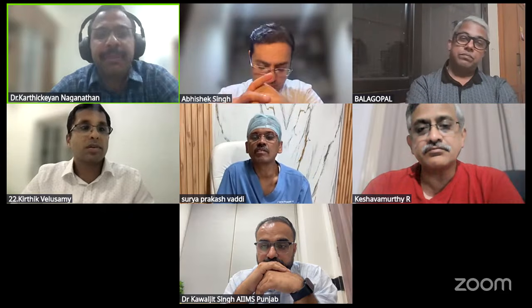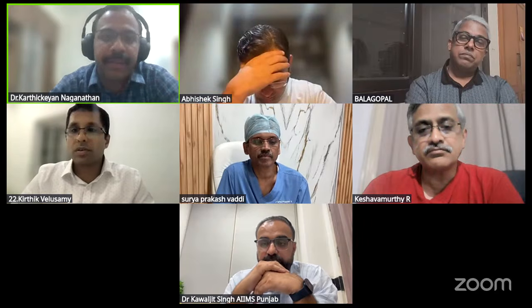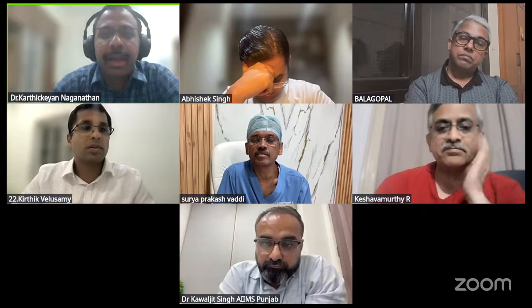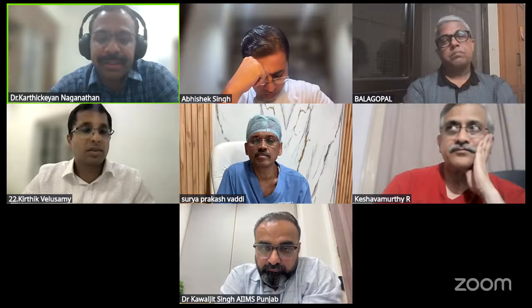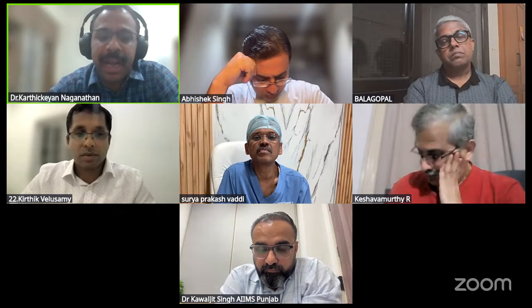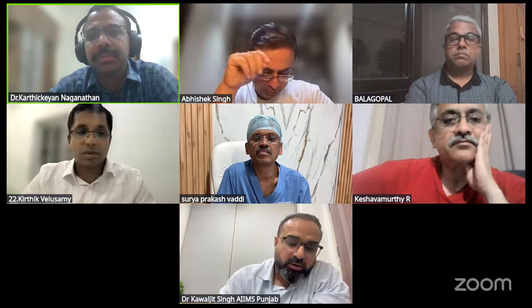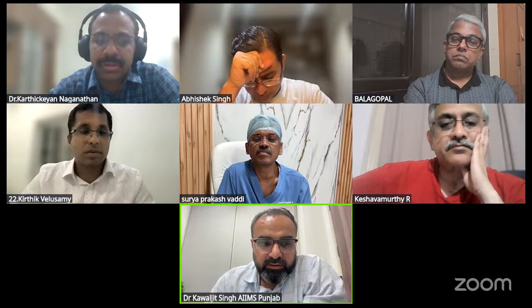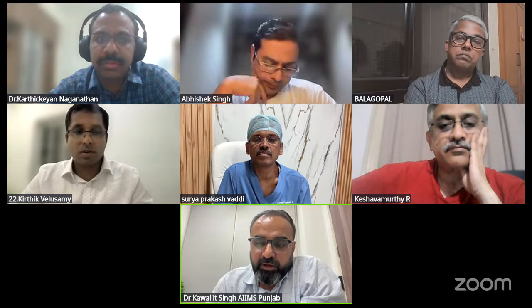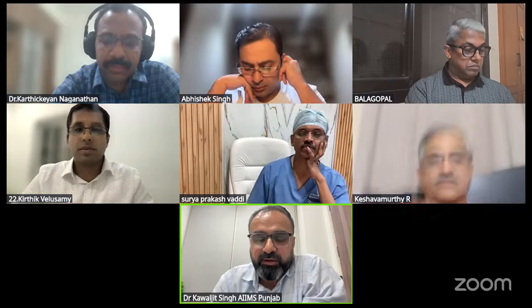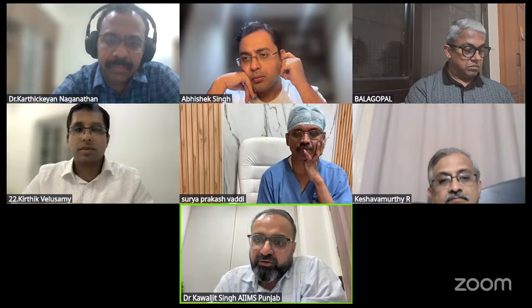Thank you, sir. I will add steam autoclave also, and also to train the staff nurses adequately on the sterilization process. So autoclave, high-level disinfection and the staff. Kawaljeet sir, how long can an instrument remain sterile after processing if it is not used? I feel it depends upon how well the time duration is documented, how well the record of sterilized equipment is maintained in the hospital, and how the instruments are stored, vertically in a covered cabinet. If everything is done in a proper SOP-specific manner, then the duration can be, say, up to 2 weeks or a month or so.